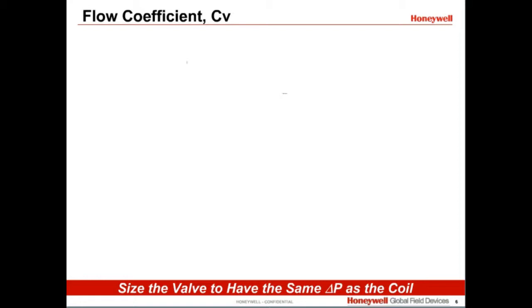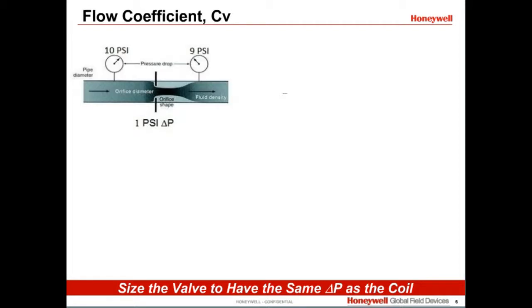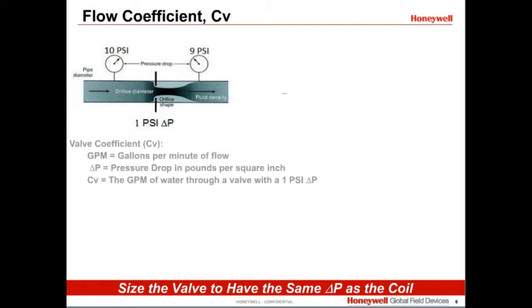A valve creates some resistance to flow. This can be measured by the pressure drop across the valve. Flow coefficient, or CV, is a measure of this pressure drop. It is the flow in gallons per minute through a valve at 1 psi pressure drop.